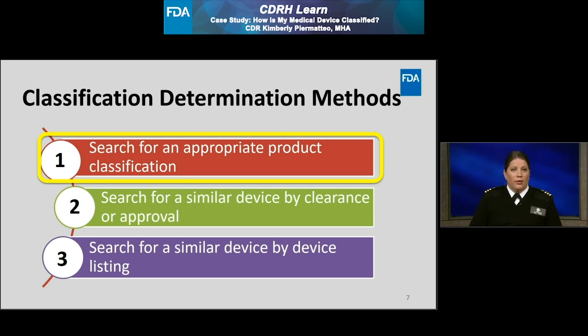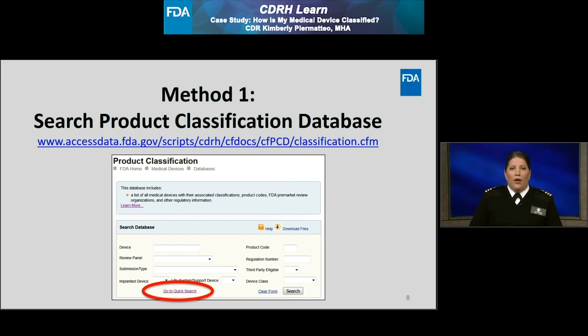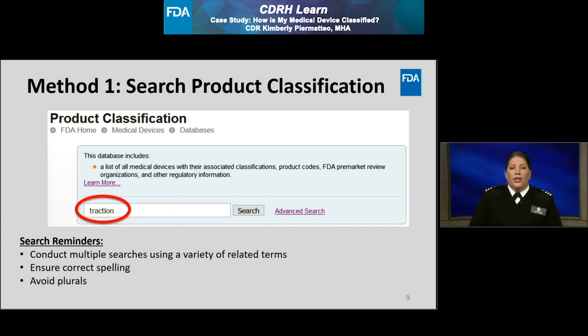First, we will look at method one. To search for an applicable product classification, I will be searching the FDA's public product classification database. A screenshot of the product classification database is provided on this slide. You may search the various fields provided. However, I recommend you go to the quick search feature, which is circled in red on this slide. From the quick search, you can search using a keyword. For this example, I'm going to search using the keyword traction. I could conduct multiple searches using other words, but I feel this one most appropriately describes the example device. When searching the product classification database, remember to conduct multiple searches using a variety of key terms so that you ensure you capture as many potentially related product classifications, which you can then narrow down.